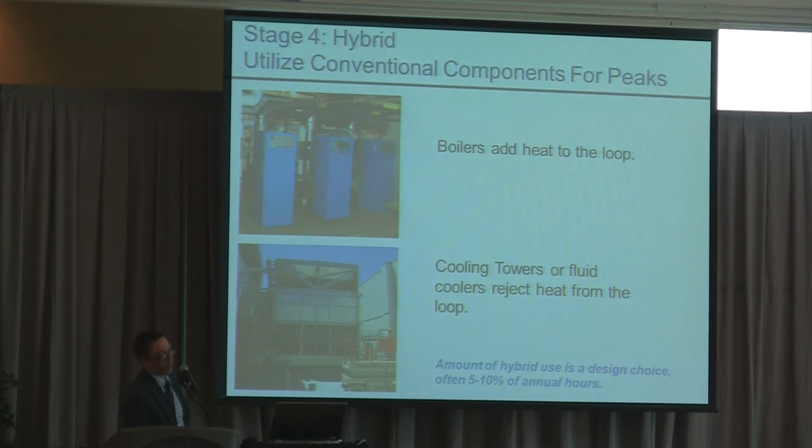Oh, and it's worth mentioning, in some of our retrofit applications, we've been able to use existing boilers or cooling towers on some of these systems. So there was no added expense to add the hybrid component. And if they were partway through their service life, because now they're only running maybe 5 or 10% of the hours of the year, instead of thousands of hours per year, then the life of that existing equipment has been extended pretty dramatically.